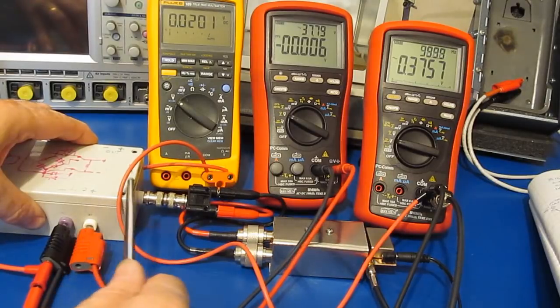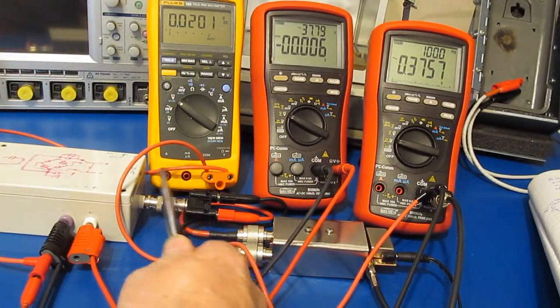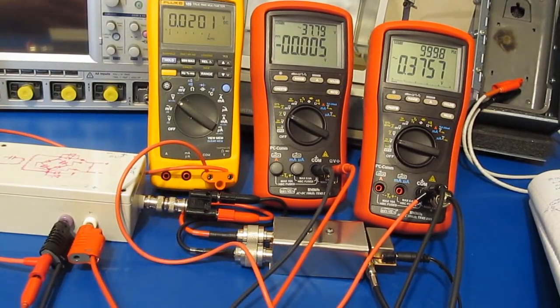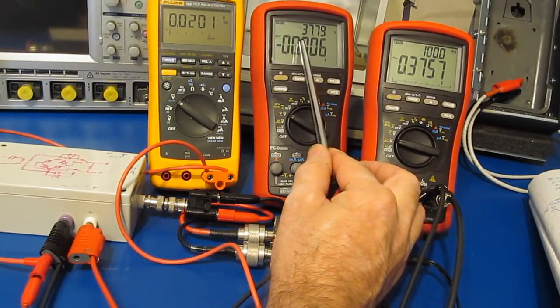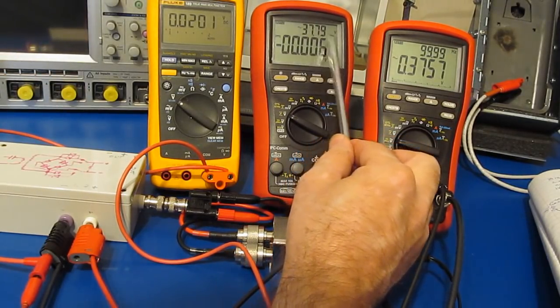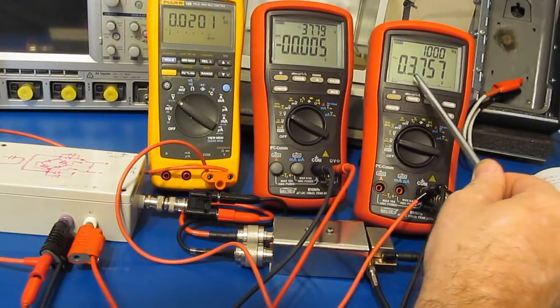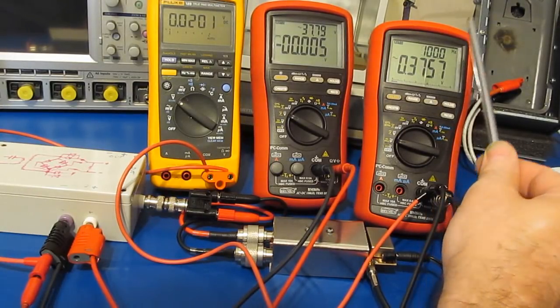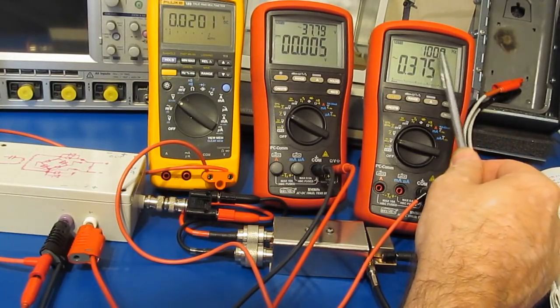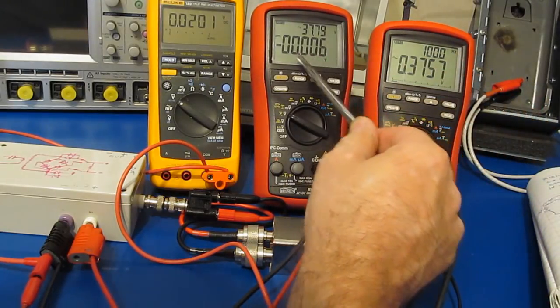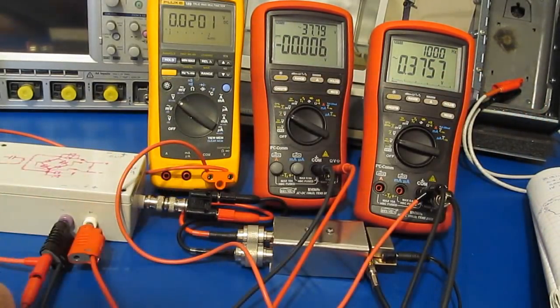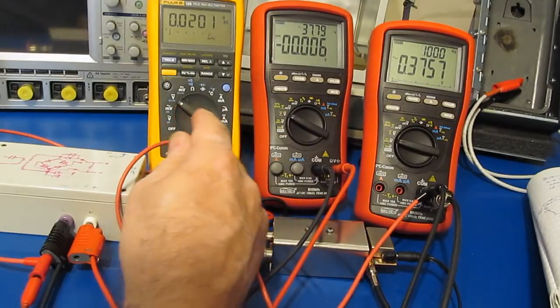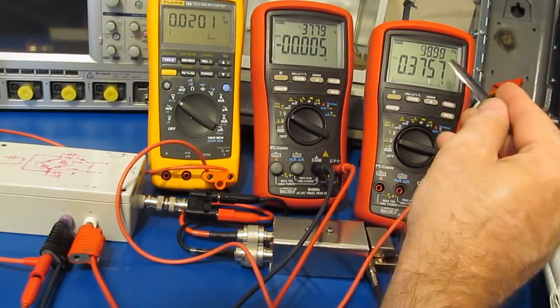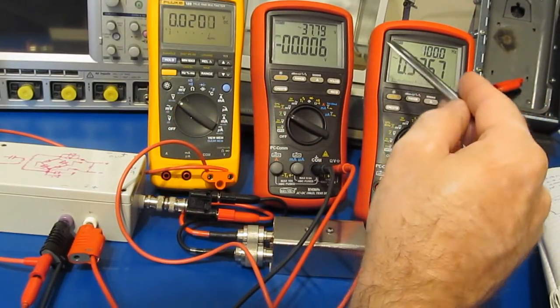One is just banana connectors versus this BNC. It just makes it more flexible when I use this box. You can see the output of our transformer is roughly 37.79 volts. The output of our probe is 37.57 volts. You can see it's at 1000 hertz, and there is no DC offset. What I'm going to do now is go ahead and start to turn up our power supply, and let's see what effect that has on the output of our probe.